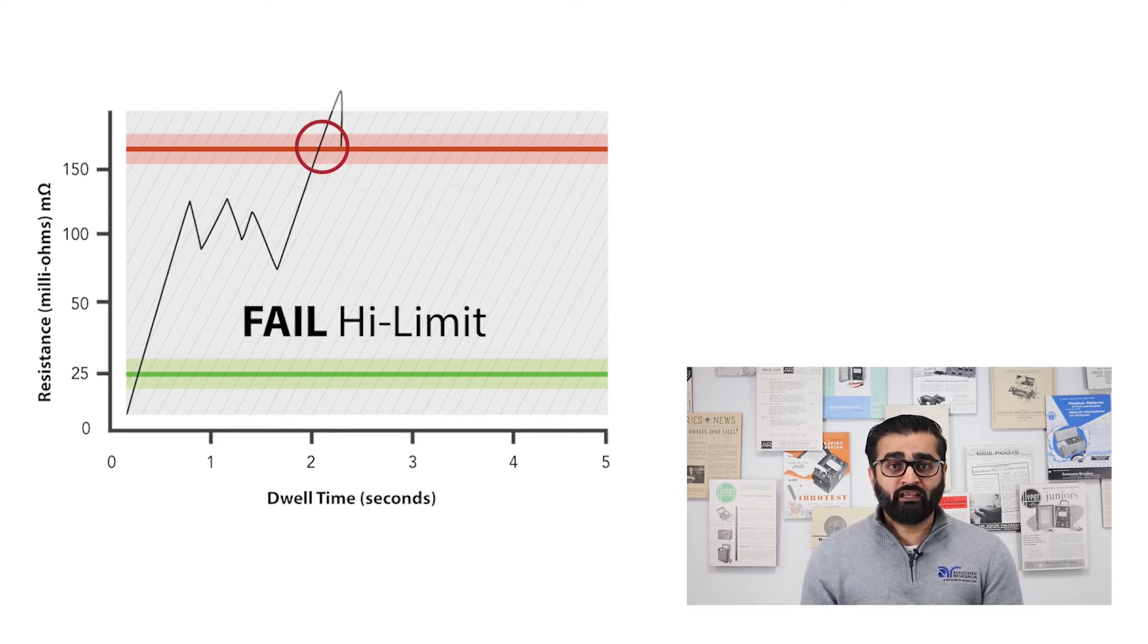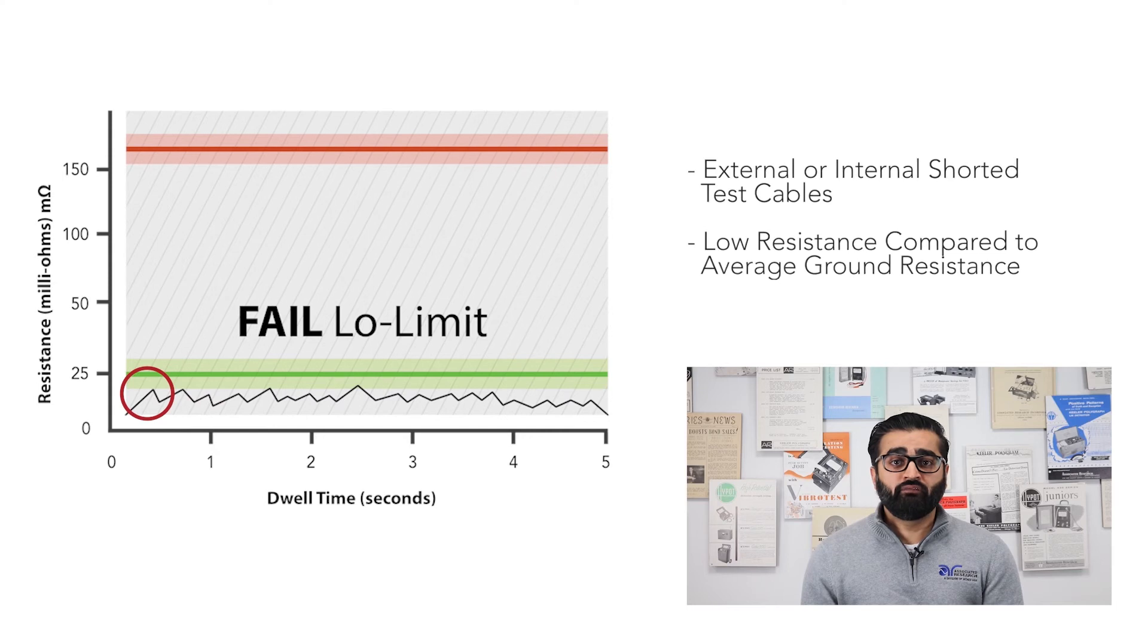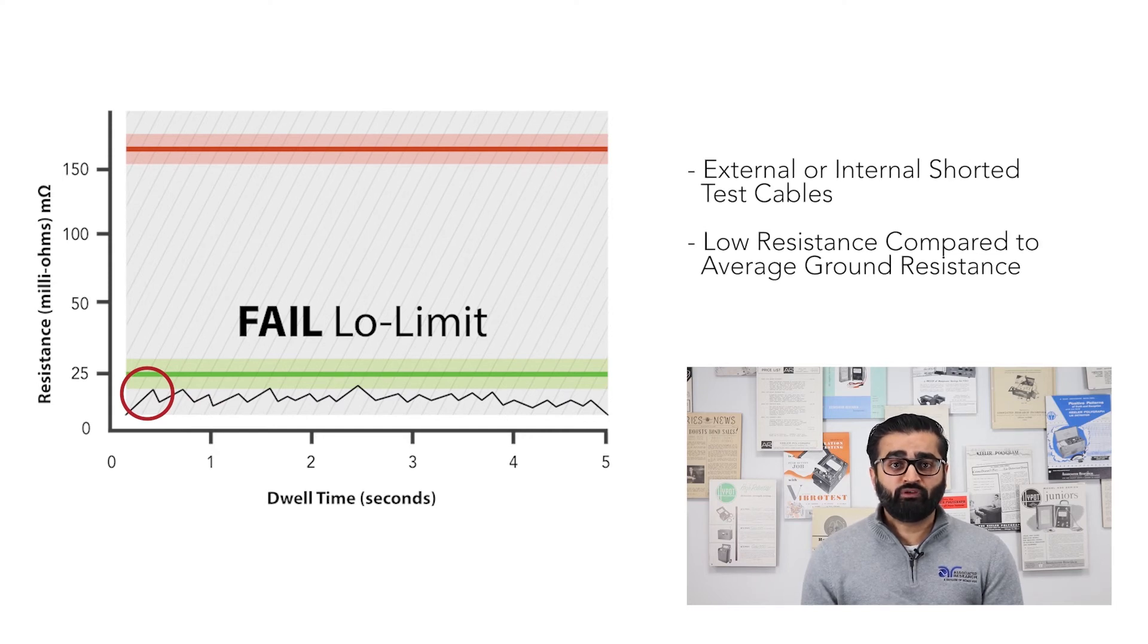If the resistance exceeds this high limit parameter, this is considered a high limit failure and the ground bond test has failed. If there are types of shorts between the test cables or equipment malfunctions, the ground bond resistance will read a small value, for example below 25 milliohms. While ultimately this small value is desirable, the low limit parameter can be utilized in order to flag measurements that are well below an average value for the given test.